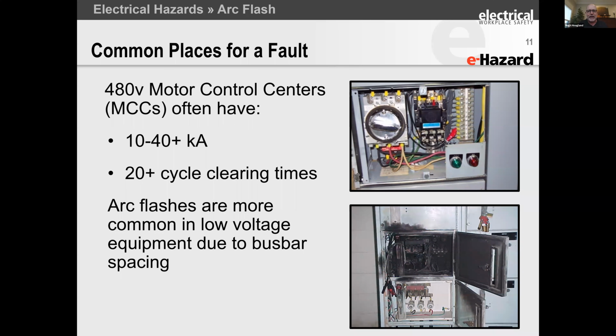So it went three-phase 480 in the bucket because the wire probably had a bad piece of insulation, which is what we determined in our finding. Even though what he was working on was really low risk and a low level of arc, it caused something else that wasn't properly protected to blow up. It was an older style of equipment, probably built before 1991.